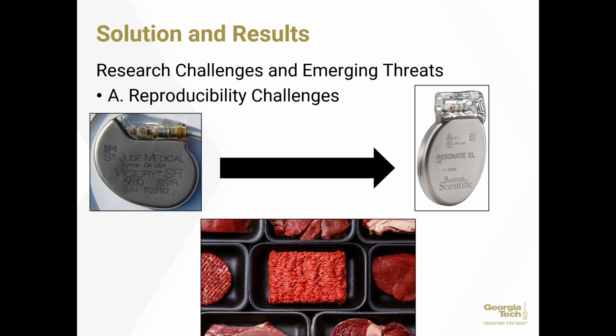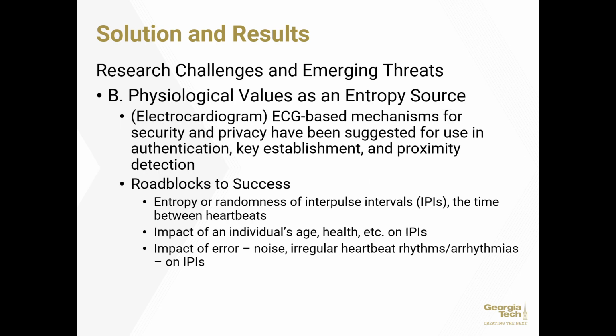Secondly, the use of food-grade meat as a phantom or human tissue simulator is also a problem. This method does not lead to reproducible experiments, possibly due to the introduction of uncontrolled variables that can affect the impedance of the tissue or propagation of signals in the phantom. Instead, researchers should use a calibrated saline solution with electrodes to inject the appropriate simulated physiological signals.